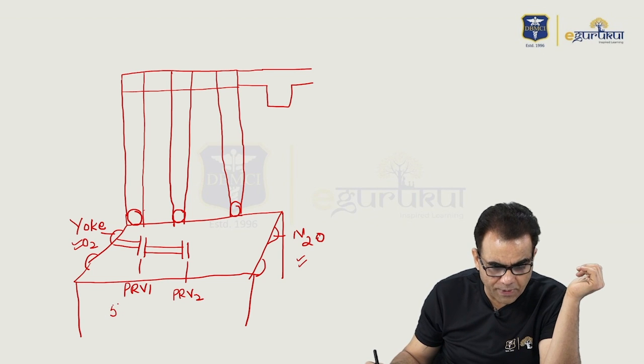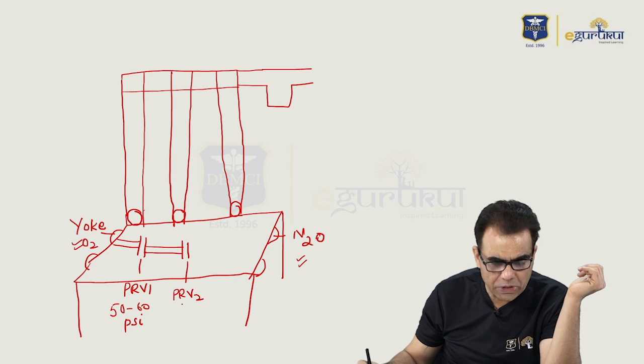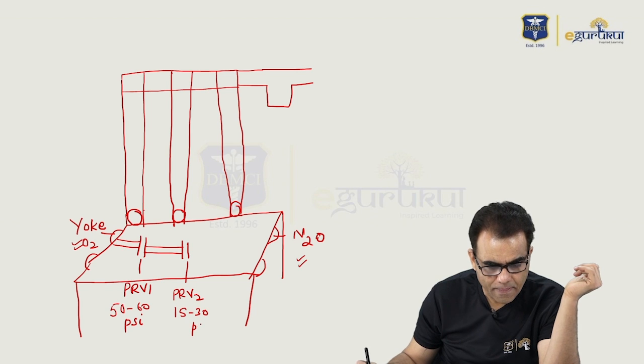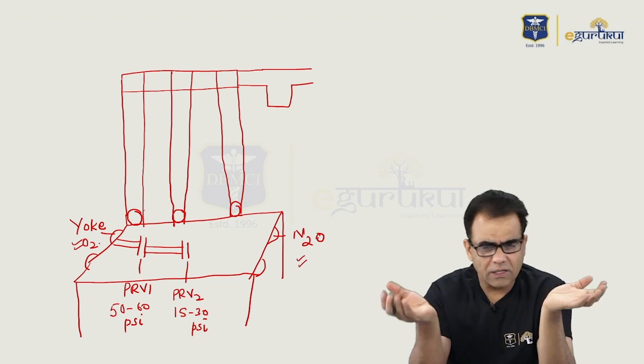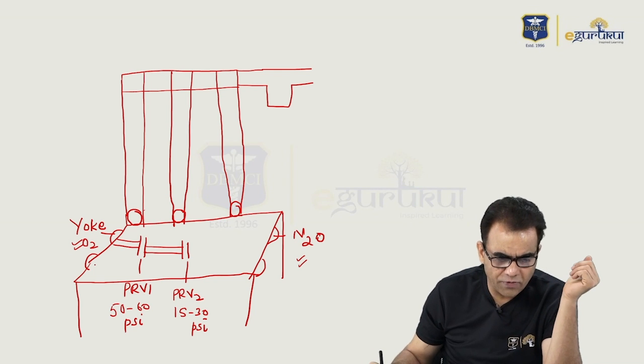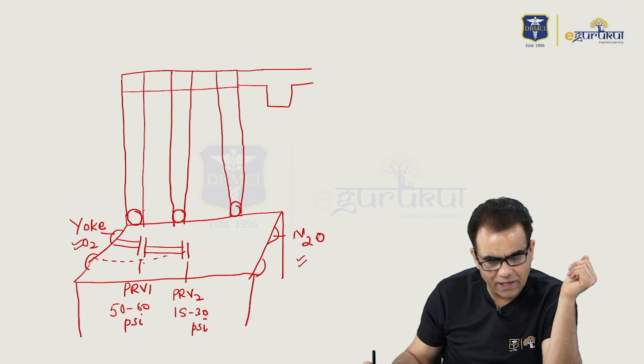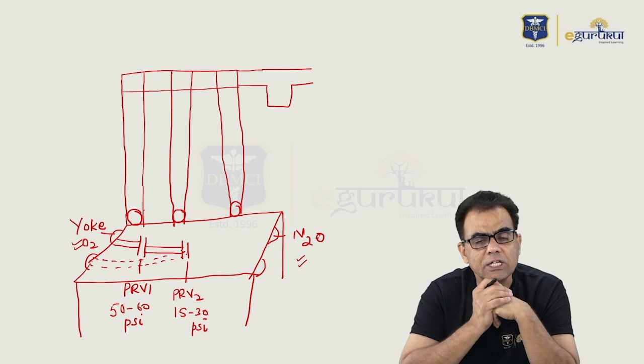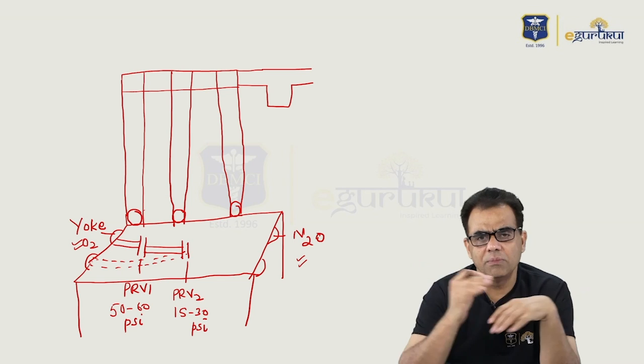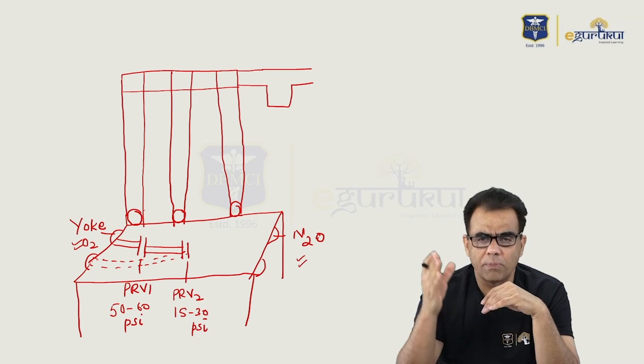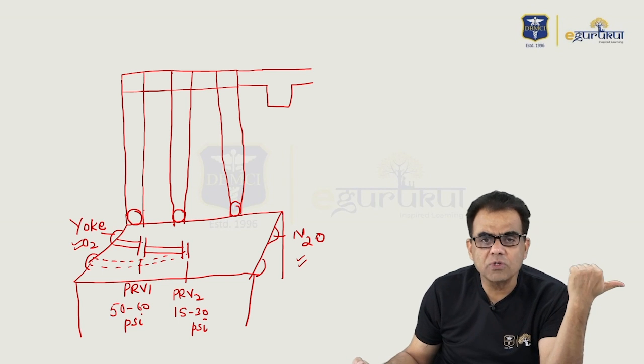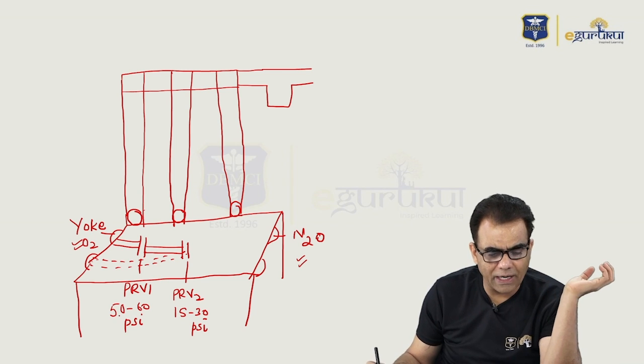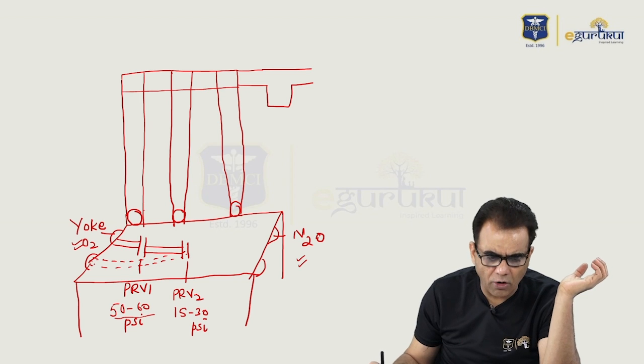There are two stages of pressure reduction: the first will reduce the pressure to 50 to 60 PSI, and the second reduces it to 15 to 30 PSI. Now, if gases are coming through central supply, they are already coming at around 60 PSI, so in most modern machines they are directly attached to the second stage pressure reducing valve, which will reduce it to 15 to 30 PSI. These pressure reducing valves have many names: primary pressure regulator, secondary pressure regulator, pressure regulating valve 1, pressure regulating valve 2.